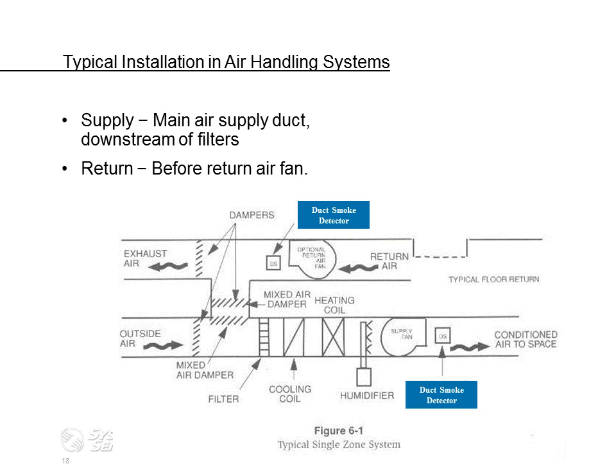And again, another typical installation in the air handling system. On the supply side, you see the main air supply duct, downstream of filters, and then if it's on the return side, you'll see it's before the return air fan. A lot of people will ask, well, why would you put it in the supply? Why would you put it in the return? We put this out here so that you can see it because depending on what standard you're designing to, one says that you have to put the duct detector in the supply side, the other says you put it in the return side, and there are some applications where you require it in both supply and return, depending on the size of the unit.